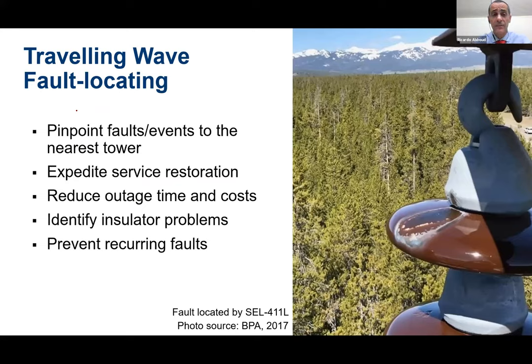In terms of transmission systems, we can have traveling wave fault locating in the digital relay, so you don't need an additional traveling wave system. You can have line protection relays with traveling wave fault locating. With this feature, we can pinpoint faults or events in the transmission line, because sometimes you do not have a fault but a flashover, an incipient fault that will not cause a breakdown of the insulation. But the traveling wave can detect that event and tell you: this transmission line is having incipient faults in this location. Go take a look if it's vegetation growing below the line, or an insulator that has some dirt on it.